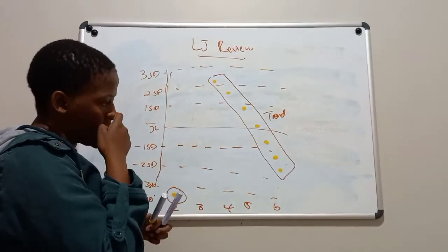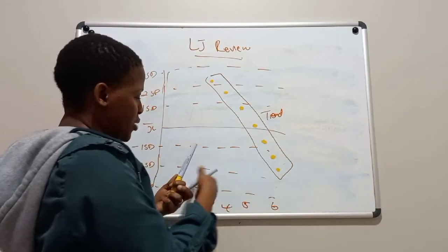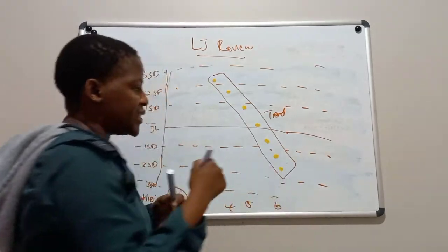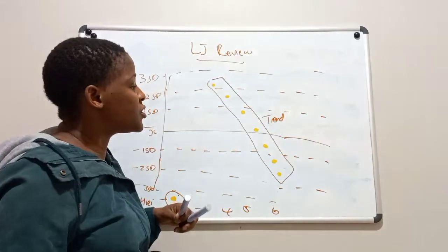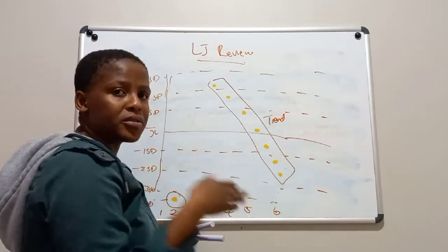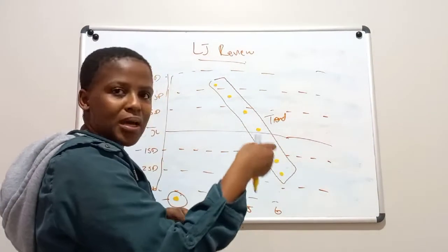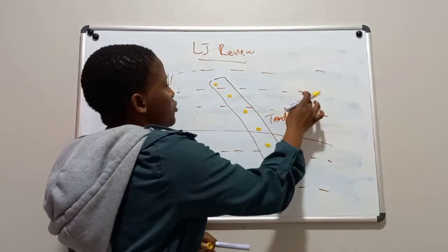And another thing that they will look at is shifts as well. So shifts, it's when you have, let's say we're having a trend here. From this point on day 6, and then probably you calibrate because you saw this trend, and you were querying the calibration status, and you decide to calibrate because of the cal stability. So as you calibrate, after calibrating, when you run your QC sample again, your values shift to the other side. So it's a movement from one side of the mean to the other side of the mean.